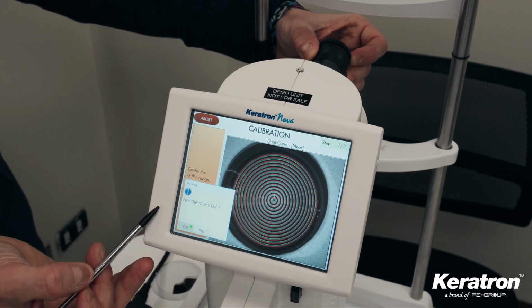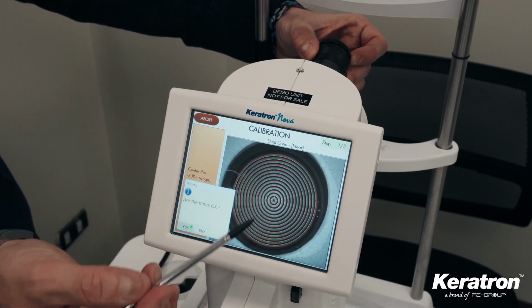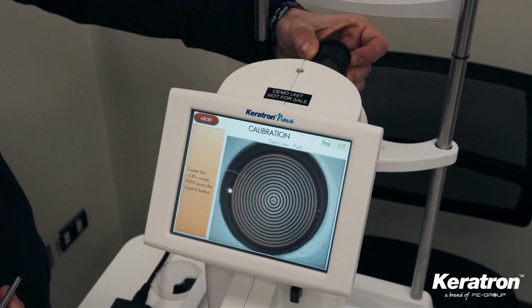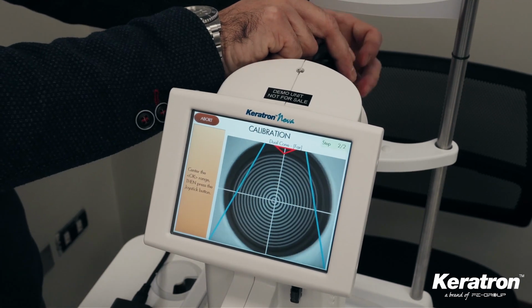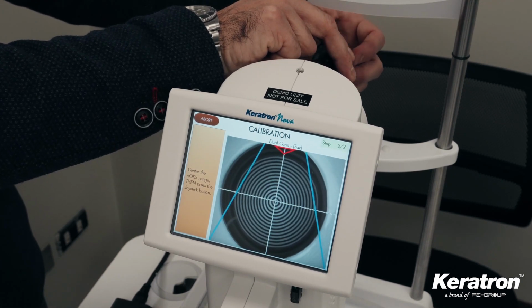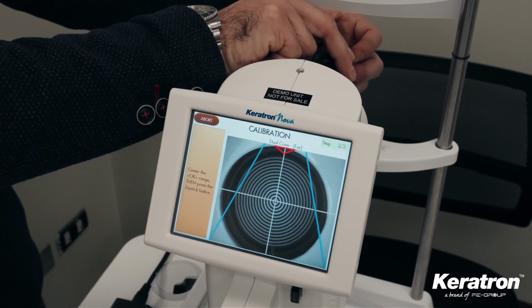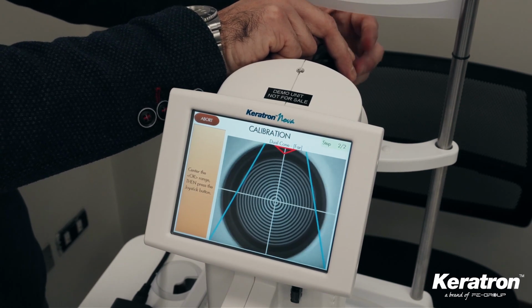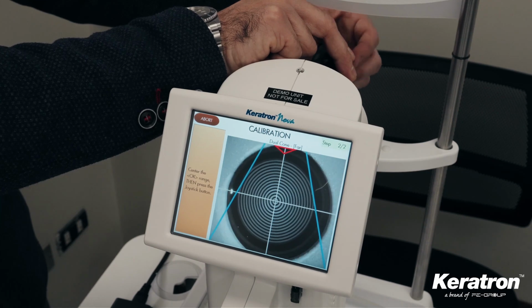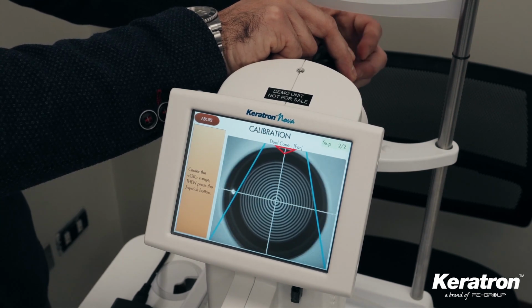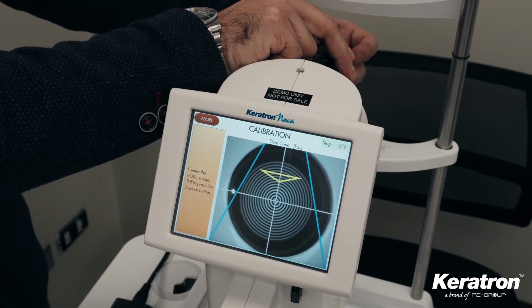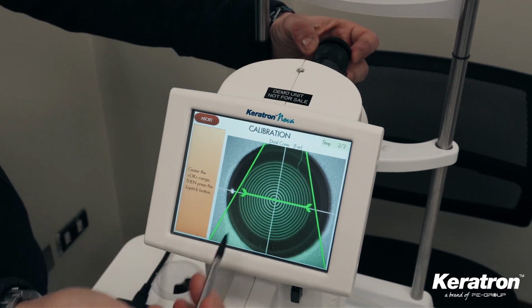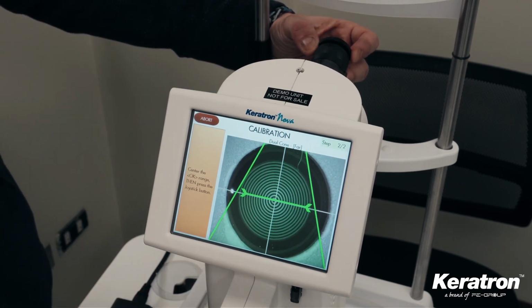Once this is done, we proceed with a second acquisition step because we need to calibrate both sensors of the cone, the external sensor and the internal sensor. So we unscrew the ring on the calibration sphere more widely, of course, until we position the sensor so that it is aligned with the center of the rings. Once the green cross is perfectly centered, we can press the acquisition button again.